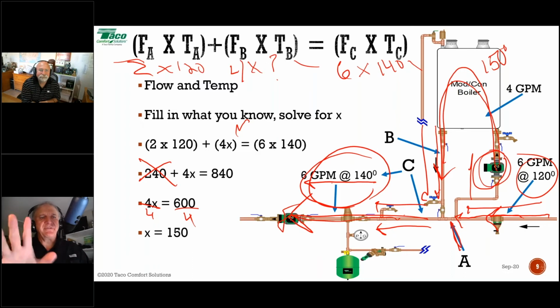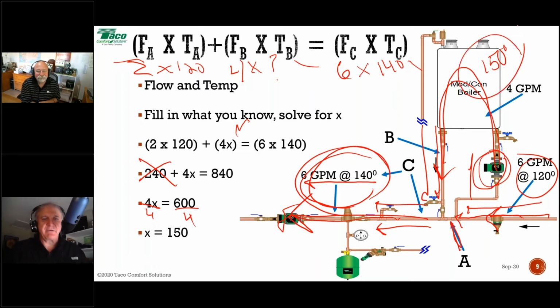So that's one way to figure this out. Just understand, if I need 140 here and I set the boiler up to make 140, I got nothing. You've got to have at least an idea of what the boiler has to be in order to deliver the temperature that you need.